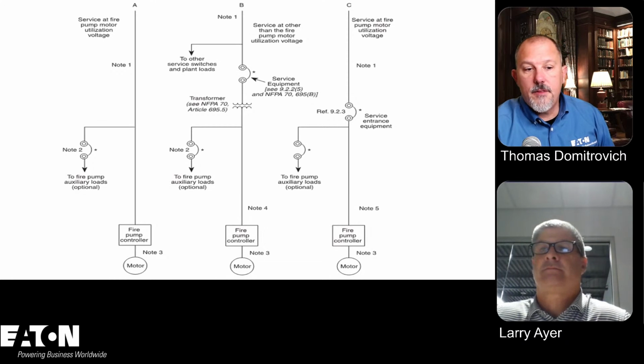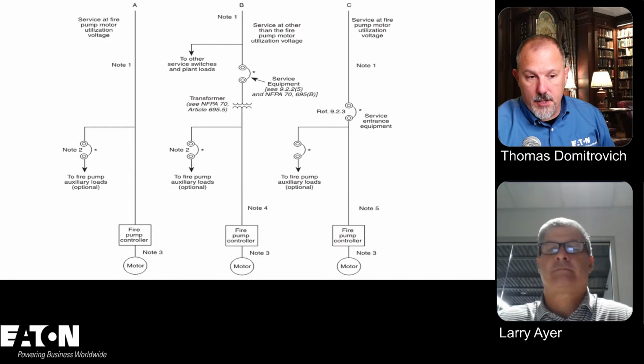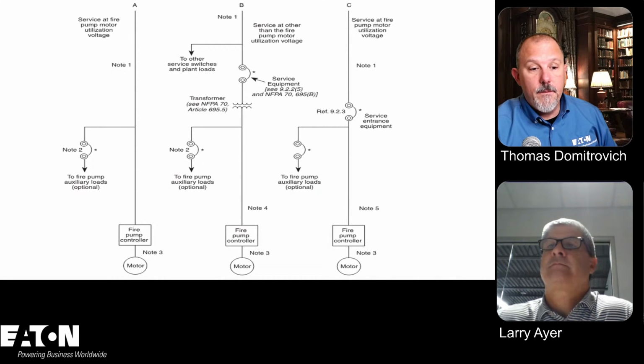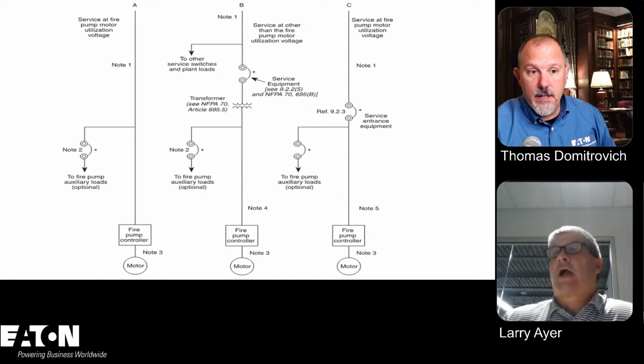Yes, and Mather is in New York City, so he sees a lot of fire pumps, I'm sure, on a daily basis. The requirement for alternate power sources is located in the International Building Code, mainly Chapter 27. Even the NEC doesn't speak about that requirement. It's the building code, where the authority having jurisdiction, the AHJ, has the fire protection system. So the AHJ is going to be referencing Chapter 27 in the IBC for a lot of this stuff.